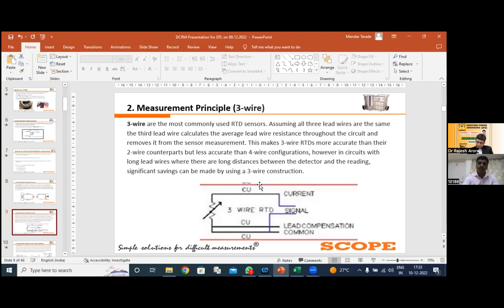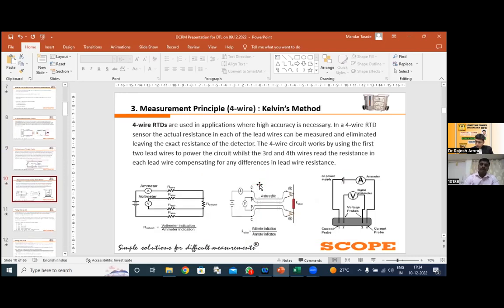This measurement method is comparatively more accurate than the 2-wire measurement method. But the most precise and accurate measurement method is the Kelvin's 4-wire method, where 2 separate cables are used for the injection of the current and 2 separate cables are used for the measurement of the resistance. So with the help of this method, we can precisely measure a resistance value which is in micro ohm or milliohm. Whatever test we are performing on the DUT, in most of the tests we are performing the test with the Kelvin's 4-wire measurement method. This is very important. That's why the cable plays a very significant and important role in this measurement. I hope this is clear to all.